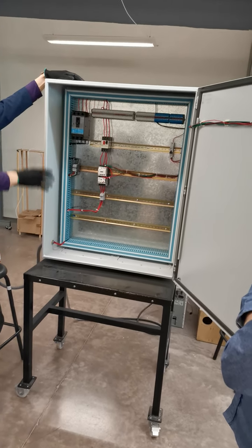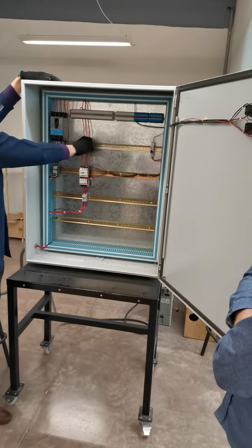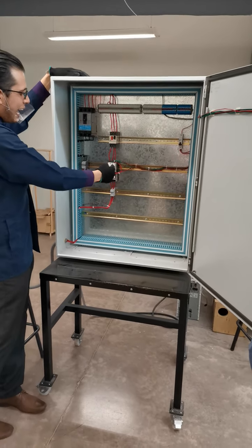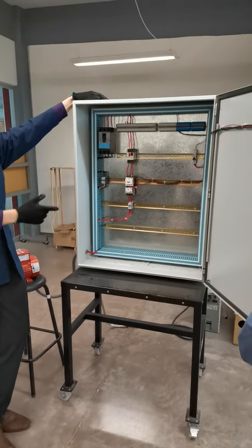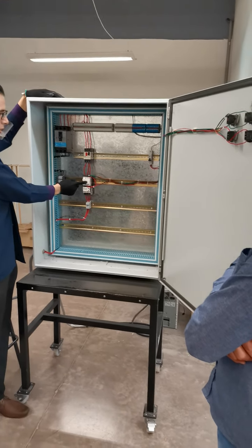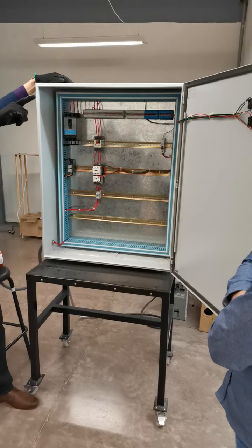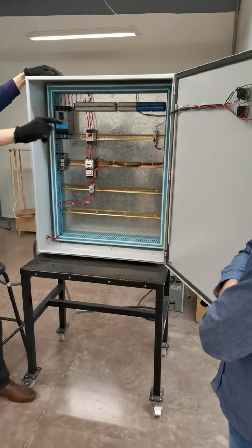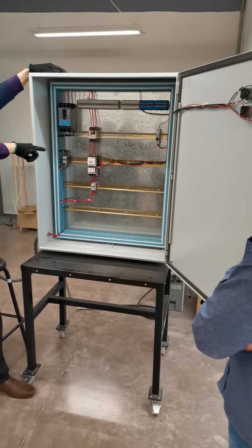Well, the one that I have just explained is the power section, because if you check, this one is the derivation for power in order to derivate it for the motor starter, and then all of this section, including the motor, is the power section. Now, talking about the control section. For the control section, first we need a signal in order to activate the contactor, right? That signal is going to come from the bottom. So we need to derivate a signal in order to energize this section and in order to energize the contactor.